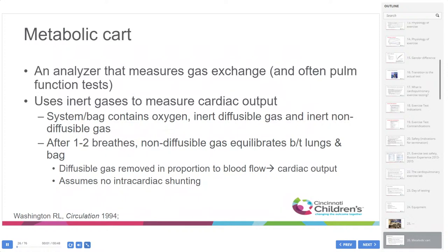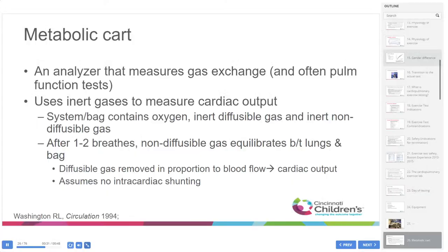A metabolic cart is an analyzer that measures gas exchange, including the amount of CO2 excreted, and is often used to perform pulmonary function tests. Certain metabolic carts can also measure cardiac output directly using inert gases: a bag system contains oxygen, an inert diffusible gas, and an inert non-diffusible gas. After one to two breaths, the non-diffusible gas equilibrates between the lungs and the bag; the diffusible gas is removed in proportion to blood flow, allowing cardiac output measurement — assuming no intracardiac shunting.